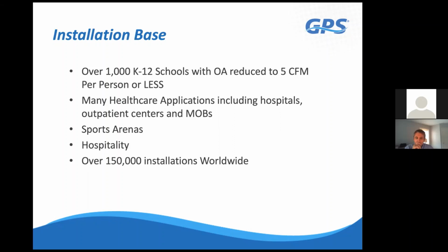On the healthcare side, as I mentioned, the technology is not used to reduce the outside air requirements, but it is used as a replacement to UV lights, as well as a replacement to carbon. It always seems that in healthcare applications, you have helicopters landing, you have diesel generators being tested, and those odors are being pulled into the building. And this technology can be used as a replacement to that carbon in those applications, as well as a replacement to the UV light to keep the coils clean and treat the space as well.